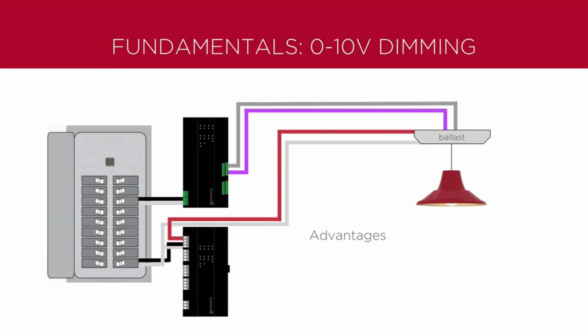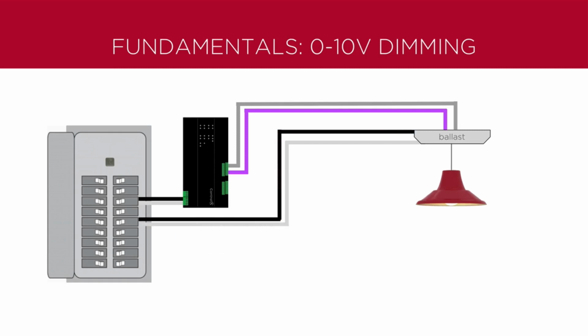The advantages for using the Control4 relay module in conjunction with the 0 to 10 volt module are simplified wiring and that it provides energy usage of the load. However, the disadvantage is that 2 separate modules are required for the fixture: the relay module for on-off control and the 0 to 10 volt module for the dimming. Or another option would be to use an external relay, which can be used with the Control4 0 to 10 volt module's relay outs in order to switch power on and off to the ballast or driver.